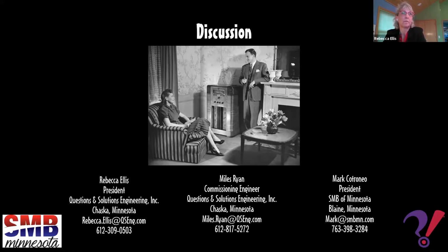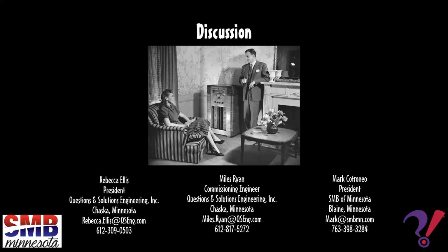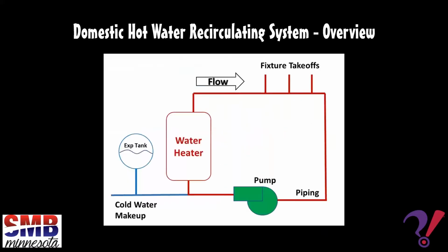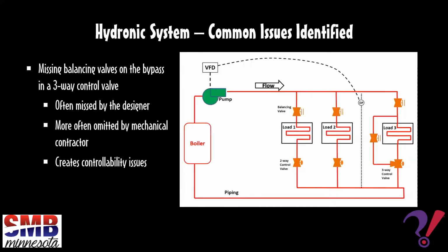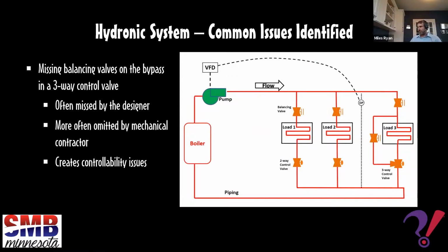Thank you, Rebecca. On one of the hydronic systems slides, Miles, one person asked about the ABVs that were clogged. Did they have a strainer? No, they did not have strainers at the individual devices. They had strainers in the system, upstream of the pumps. It was on a district heat, so it was upstream of the heat exchanger for the facility. They did not have side stream filtration, which is a recommendation currently, and they had a chemical pot feeder to do chemical treatment. Just no record of them doing it in the last few years.